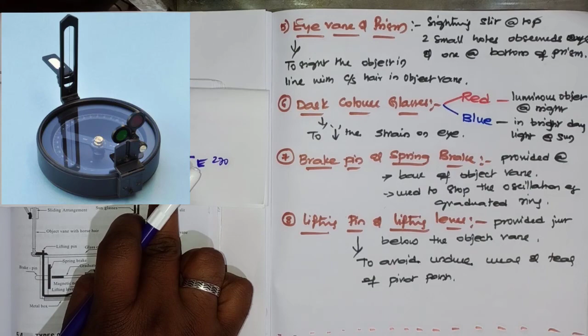And the next one is a lifting pin, below or beside the object vane, to avoid wear and tear action. Generally this will be closed while transferring your instrument from one place to another place. So at that time, in order to make the instrument free from wear and tear actions, you are supposed to close the object slit. After that, when you are ready with that one, you lift the pin.